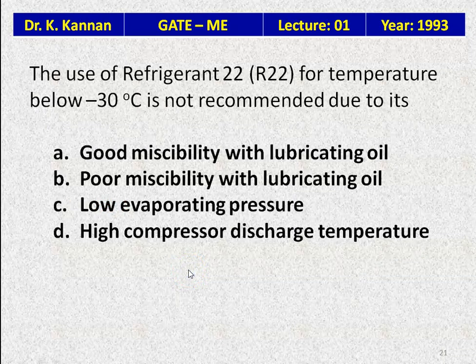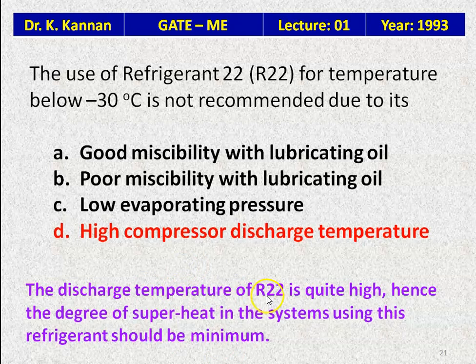Question 20: The use of refrigerant R22 for temperatures below −30°C is not recommended due to — good miscibility with lubricating oil; poor miscibility with lubricating oil; low evaporating pressure; or high compressor discharge temperature. The answer is high compressor discharge temperature. The discharge temperature of R22 is quite high; hence the degree of superheat in the system using this refrigerant should be minimum.